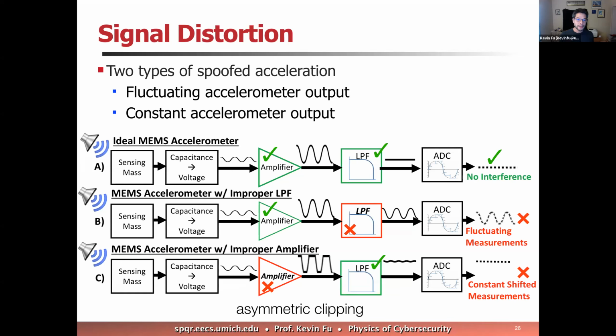A second problem with some of the accelerometers is a crappy amplifier. It does asymmetric clipping, basically chopping off the top or the bottom of the waves. And that leads to, in combination with a low-pass filter that gets rid of all the high frequencies, what does it leave behind? Basically a DC offset. So there you can control and set out a constant incorrect output from the accelerometer. Those are the two building blocks.